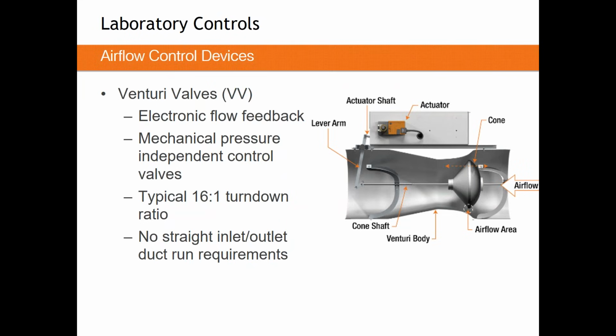So still good to plus or minus 5%, but that's without using any sort of controls or electronics. The controls and electronics come in when you'd like to select a different airflow. So if you'd like to go from 500 CFM to 1000, that's when your controller kicks in. But your controller doesn't have to do any sort of work if you'd like to always maintain 500 CFM, but your pressure in your system is changing. We're going to come back to that talk when we start to talk about constant volume and how we can apply it to equipment in laboratories and things like that.